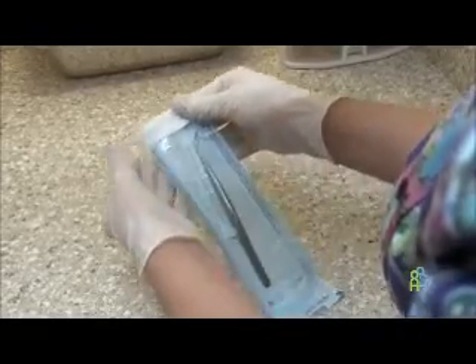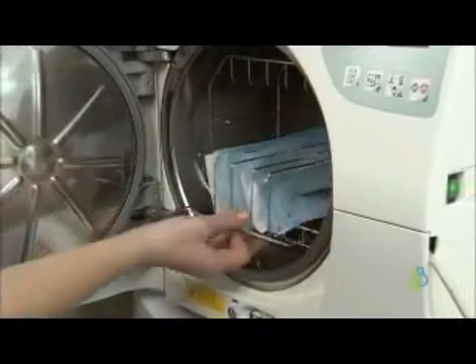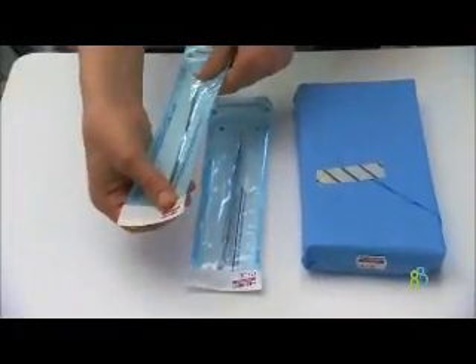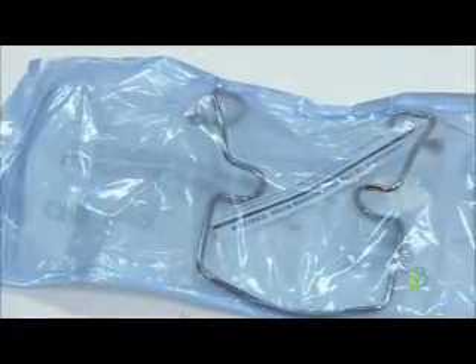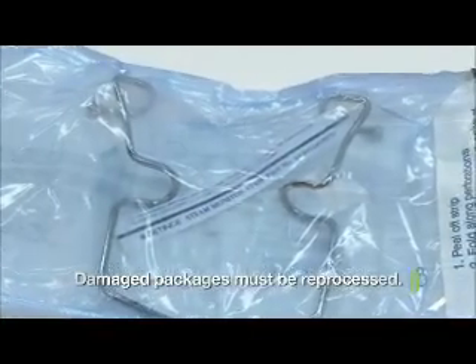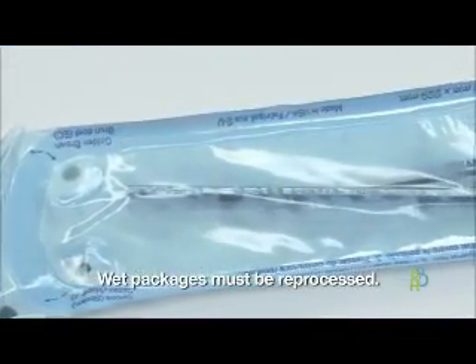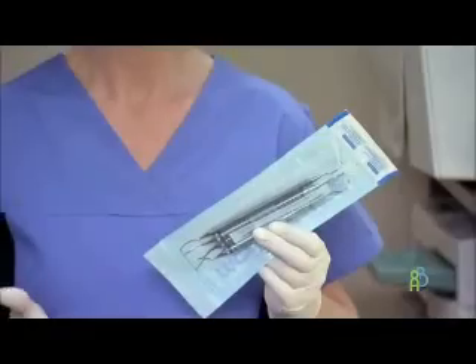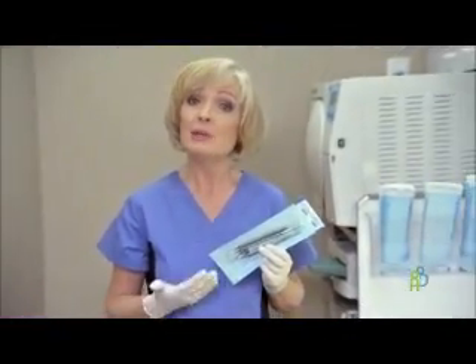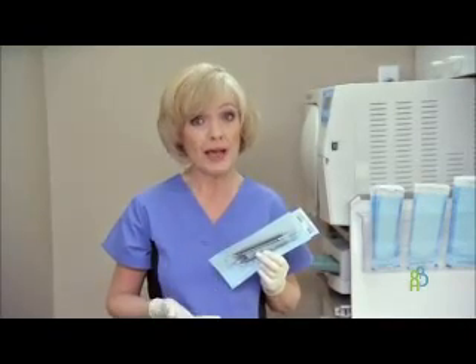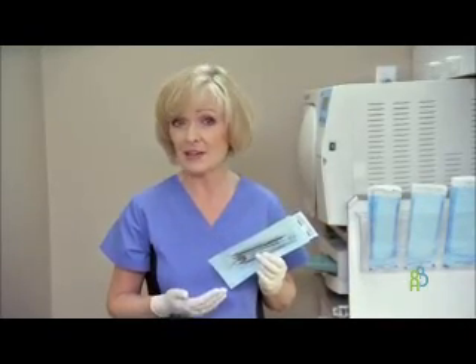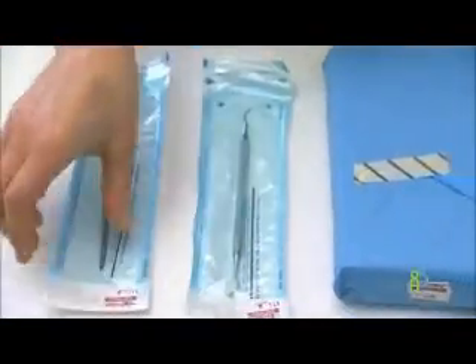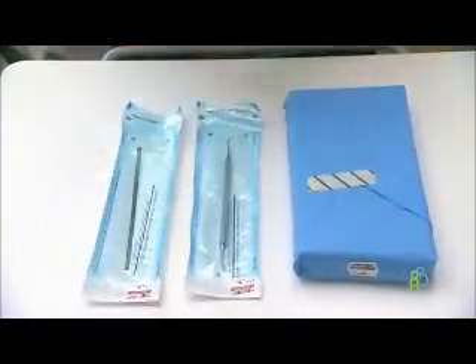Integrity of the seal should be checked prior to sterilization, following sterilization, and before final use. All packages must be dry and cool to touch prior to handling and storage. If the package seal or integrity is compromised, or if the package is wet, the items must be removed from the package and reprocessed. The number of devices placed in a package may need to be reviewed and decreased if packs are wet or package integrity is compromised following sterilization. The correct method of wrapping provides a barrier to contamination and preserves the device's sterility until it's used, and allows for sterile presentation of the devices.